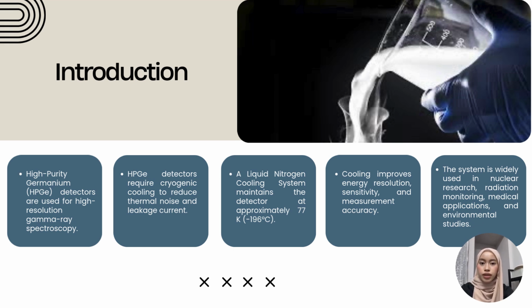To solve this problem, a liquid nitrogen cooling system is used. Liquid nitrogen has an extremely low temperature of about -196 degrees Celsius, which helps keep the detector at a very low and stable temperature. By cooling the detector, thermal noise is reduced, allowing the HPGE detector to achieve better sensitivity, higher energy resolution, and more accurate results. This is why liquid nitrogen cooling is an essential part of HPGE detector systems that are used in research, radiation monitoring, and other scientific applications.